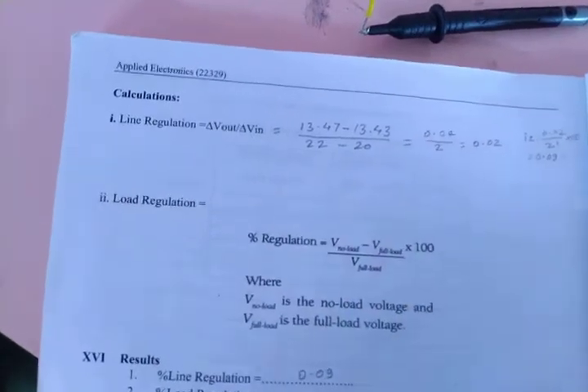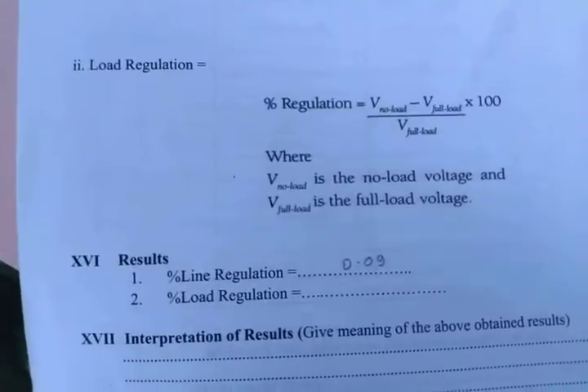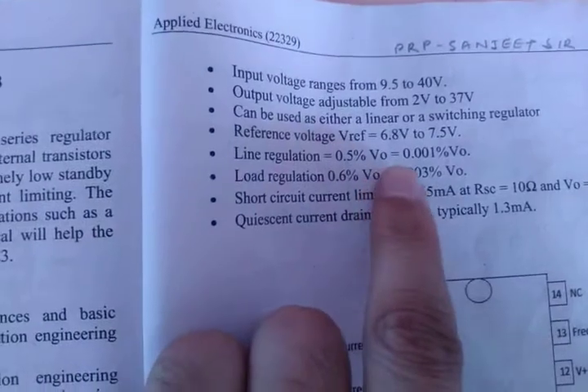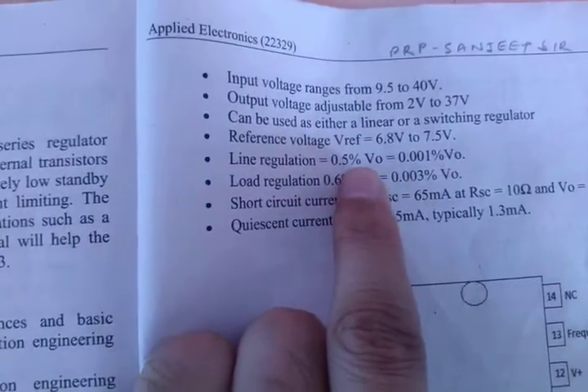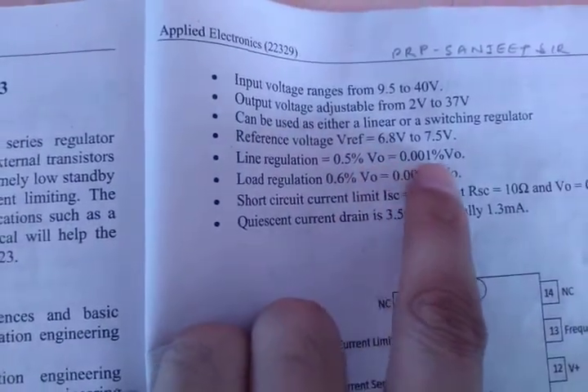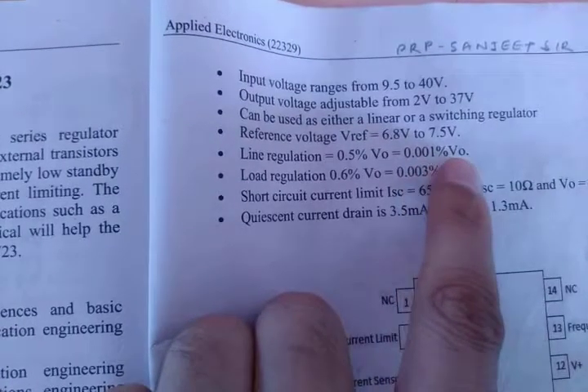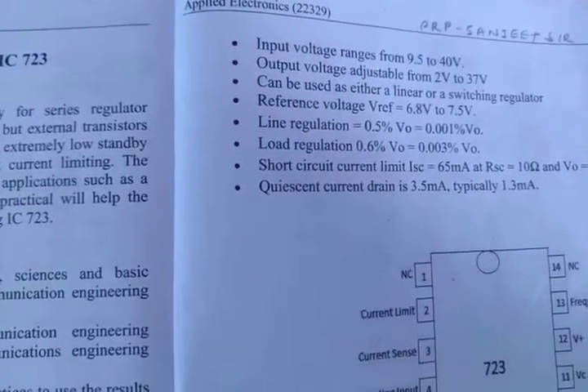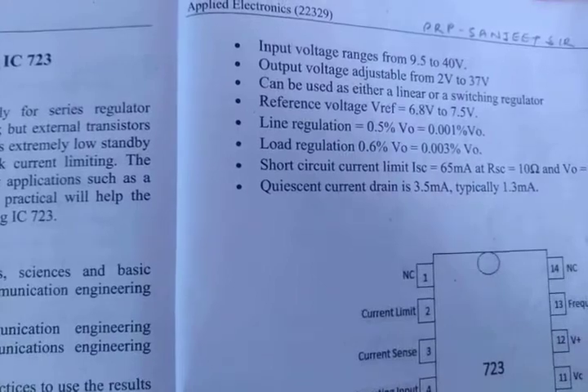So we get 0.09 as the line regulation, that is within the limit given here. Line regulation can range from 0.5% of the output to 0.001% of output, and we have 0.09, so that is within the range.